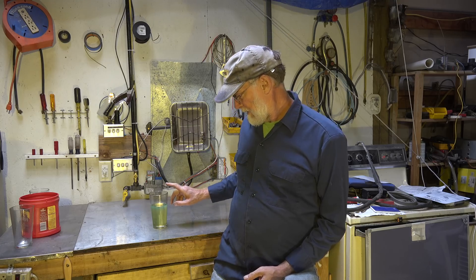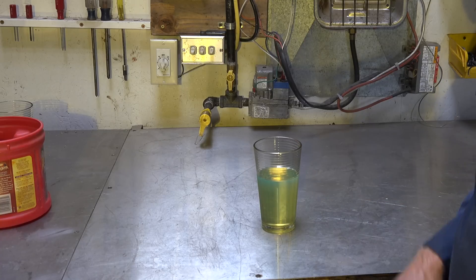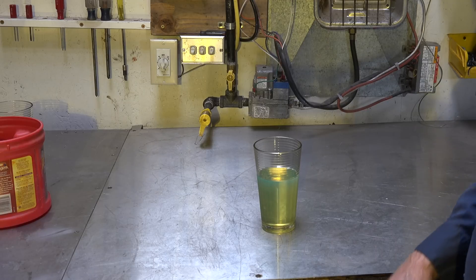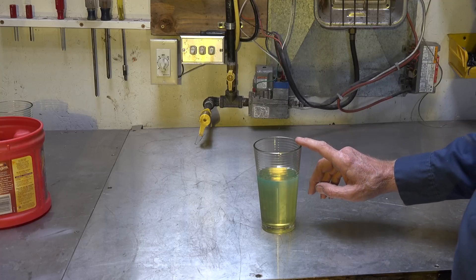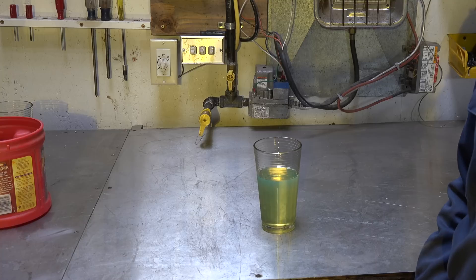This one's about number two fuel oil — this stuff right here. As most of you probably know, number two fuel oil is derived from crude oil; it's one of the distillations from crude oil. This fuel oil contains 140,000 to 144,000 BTUs per gallon, depending on the source.